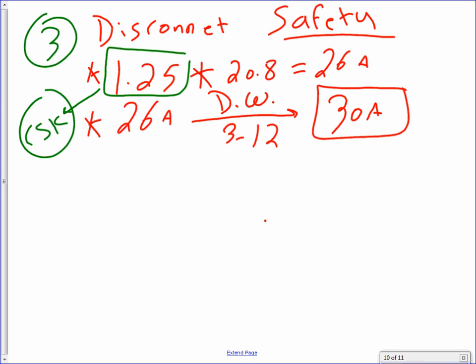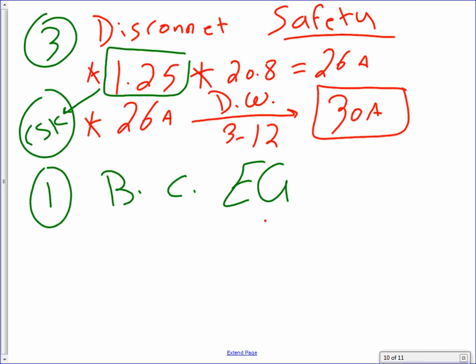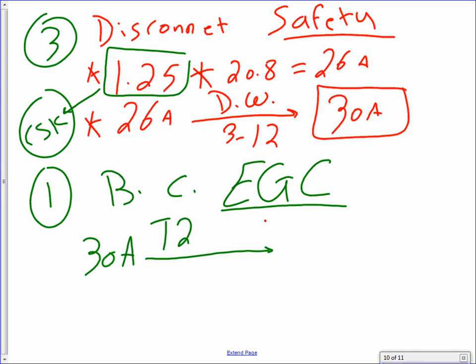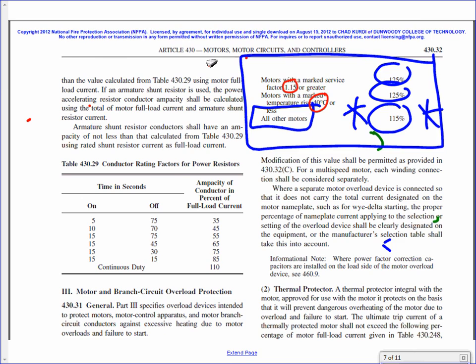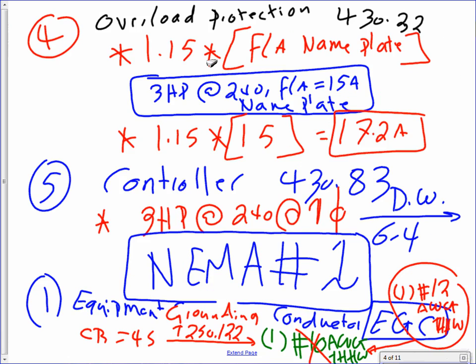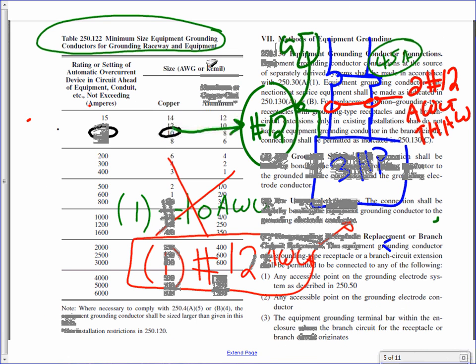Okay, last thing, I keep saying last thing, is the branch circuit equipment grounding conductor. The same thing. You're going to take the 30 amps and take it to table 250.122. What would that give you? We just did that one table. Is it number 12? There you go. Here's the table, 30 amps. Is that 20 or 30? 30 amps, number 10.